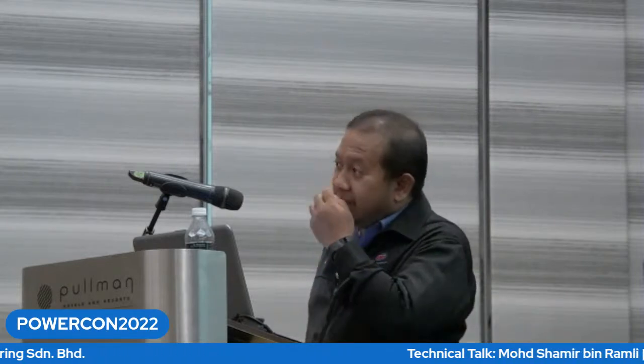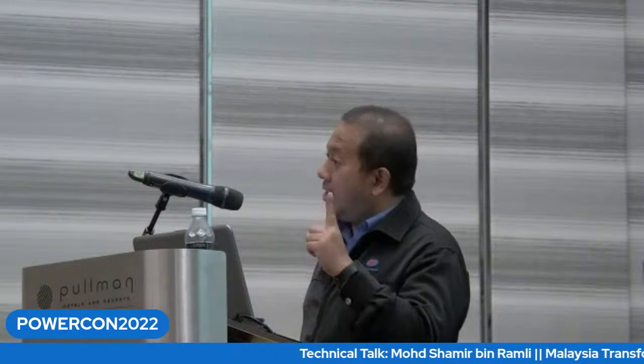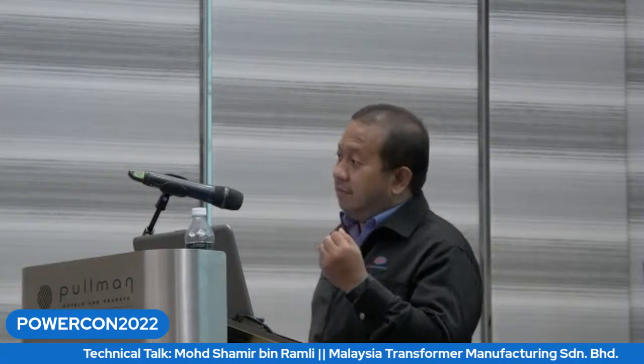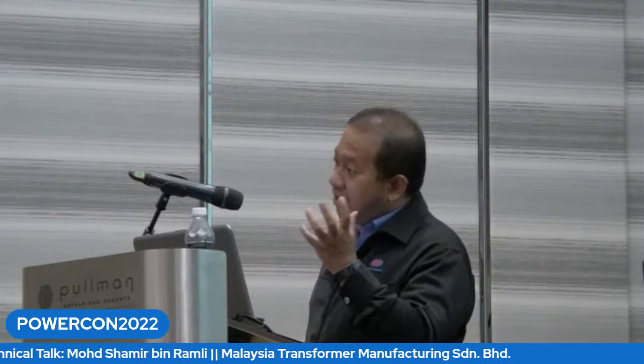So in terms of one-to-one replacement, we are very cautious. But for new transformers, we are actively looking at the viscosity and also the design of the winding to ensure we have good cooling or heat transfer within the winding. That's for the ester oil.